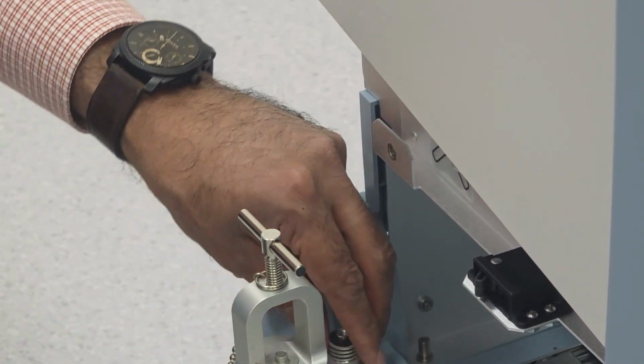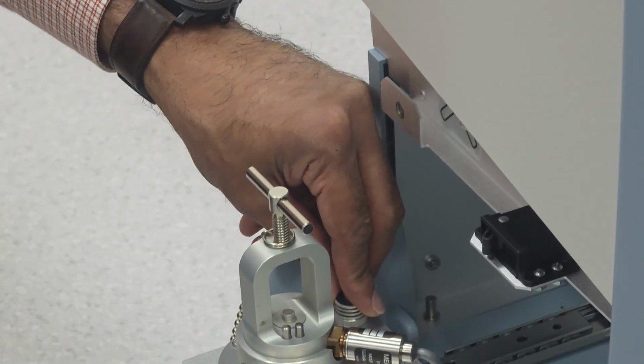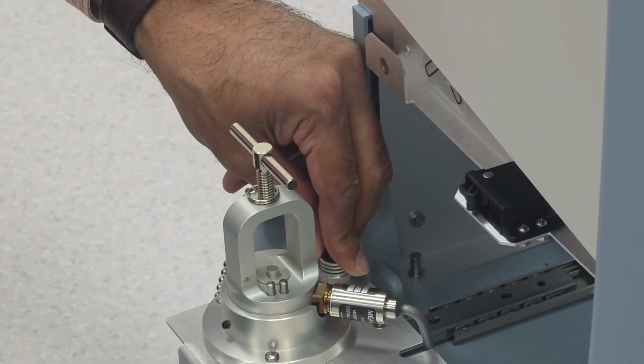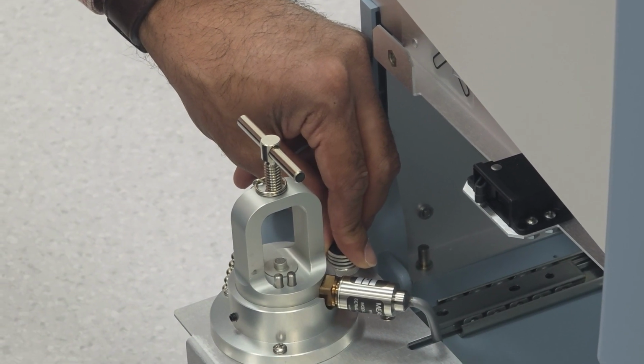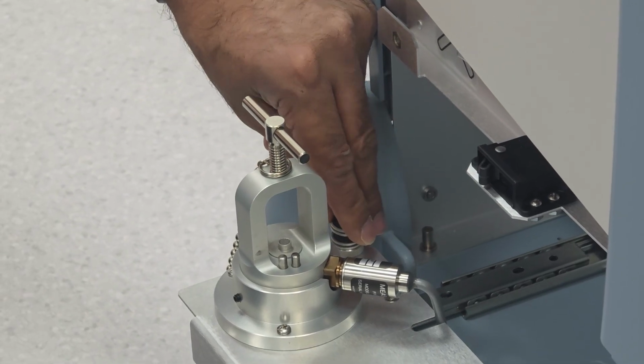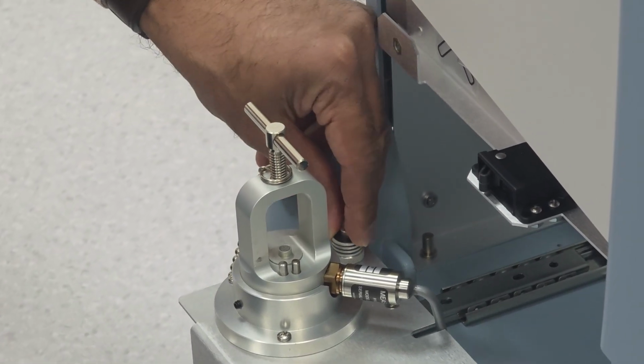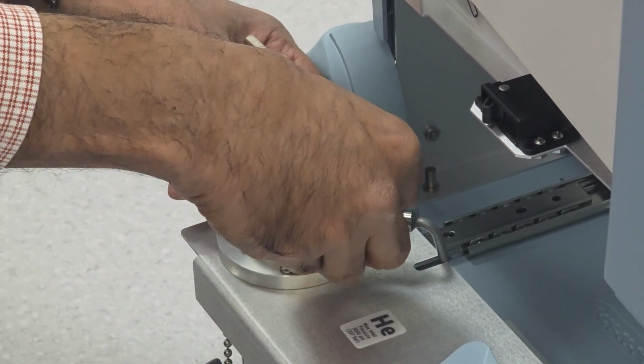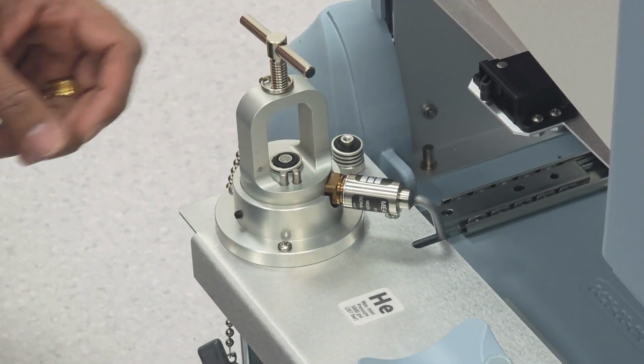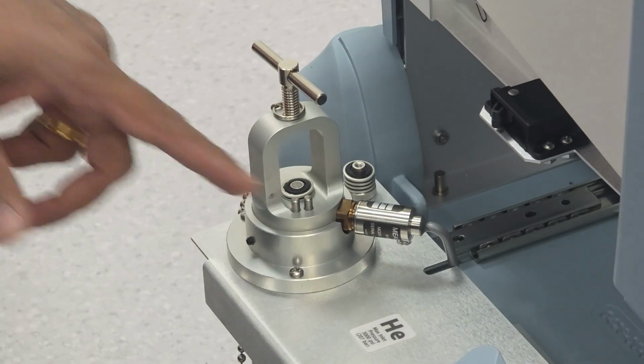Okay. So once it's finished? Yeah, but whenever you are changing the helium only, you need to replace this O-ring. There should be some wear and tear to avoid the leakage. Replace with the new one. Just take one from here and put it here. Since it's brand new, I will show you. Nothing, just keep it and push it. That's it. And you can see 2 metal rods here. It will fit with these holes. So there's only one direction.